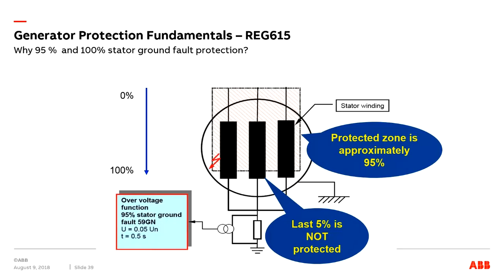So here is a look at what happens. The 95% stator ground fault protection typically measures the fundamental frequency voltage component at the generator star point, and it operates when it exceeds the preset value. By using this principle, approximately 95% of the stator winding can be protected. Which means the last 5%, which is closer to the neutral of the generator, remains unprotected.